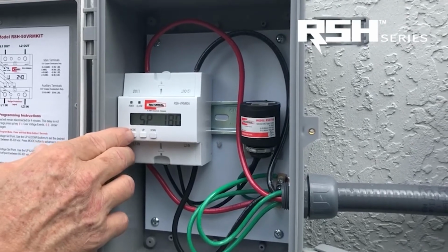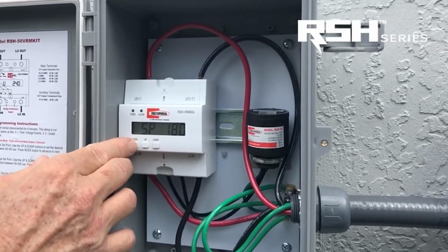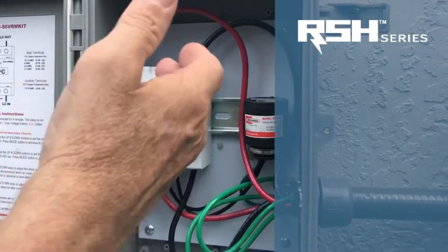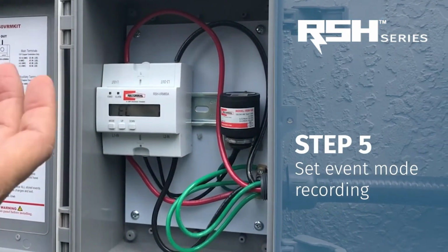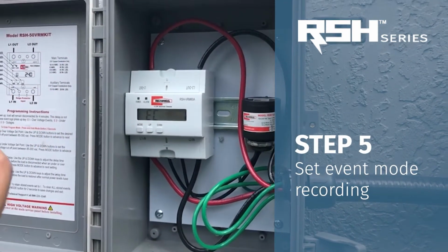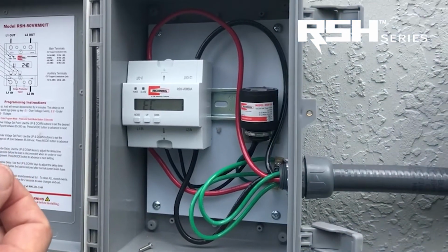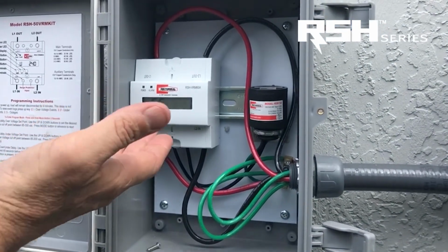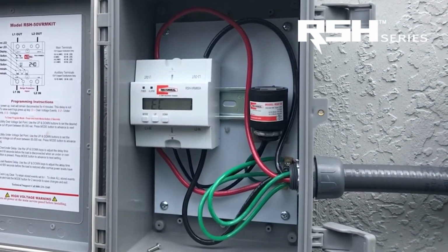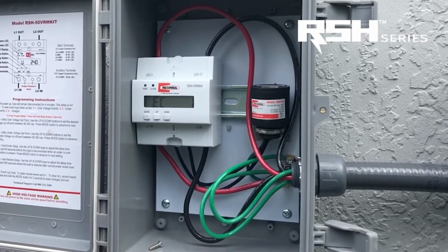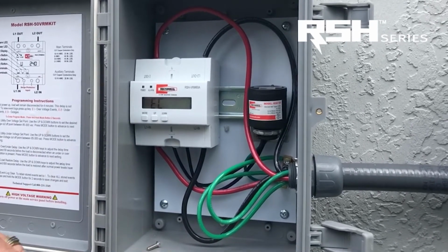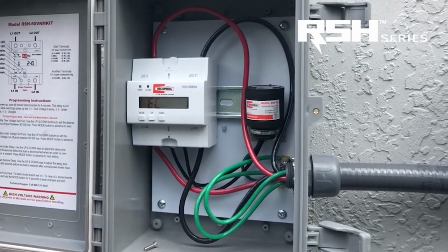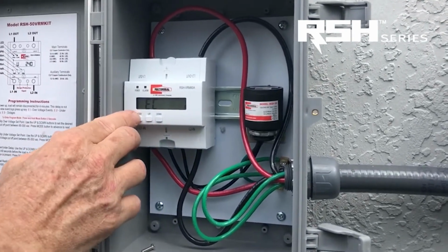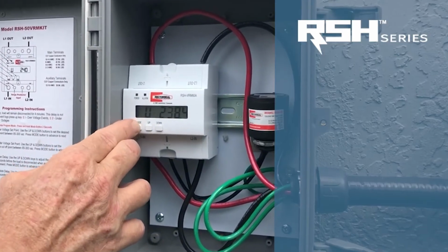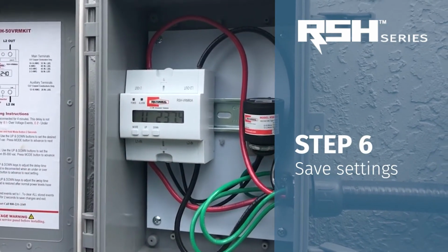There's also an event log, which is the last mode. We don't have any events recorded at this point, but this is where you can store up to 300 events. And you can determine based on the readout and the storage when you've had power related problems, either at the low voltage level or the high voltage level. And then to save those settings, press the mode button for 2 seconds and you're good to go.